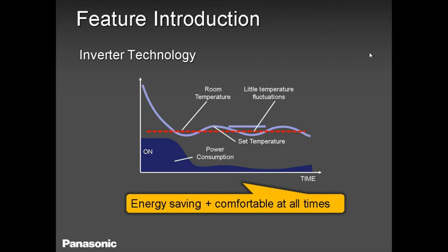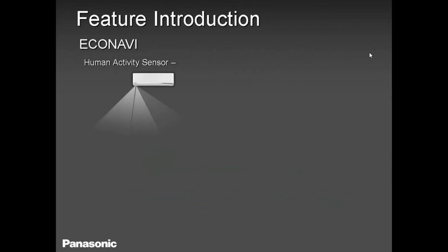Okay, I was talking about the F error code. In our Panasonic unit, we have only two letters, F as in Frank, H as in Henry. So we have the H error code and the F error code. You don't want to get the F error code because F stands for disaster. It's either the compressor or the outdoor board. Very rarely, it could be the voltage coming in is low. Very rarely, it's the refrigerant that leaked out, which is F91. Otherwise, it's either the board or the compressor. But when the outdoor board and especially the IPM is defective, you will get one of these error codes: F99, F96, F93, and F90.